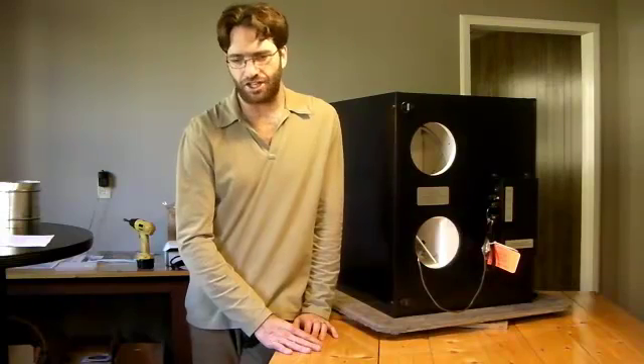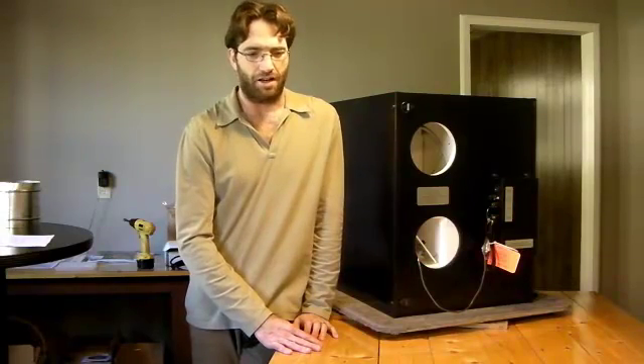Let's say the HRV set at 40 CFM is going to be the same as the ERV set at 70 CFM, as far as dehumidification goes.